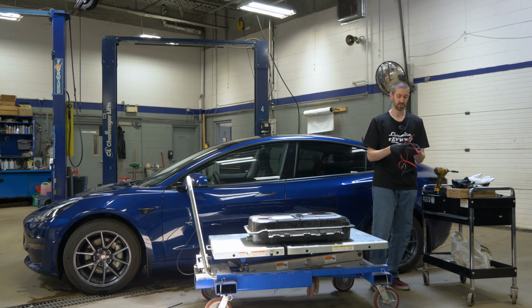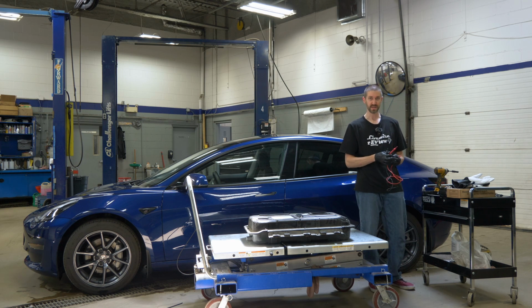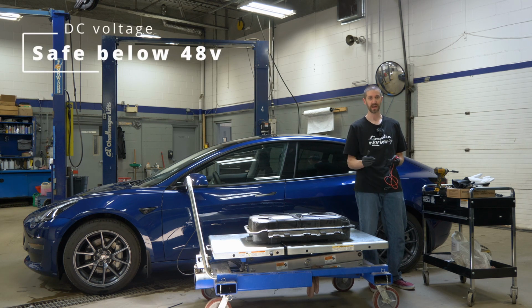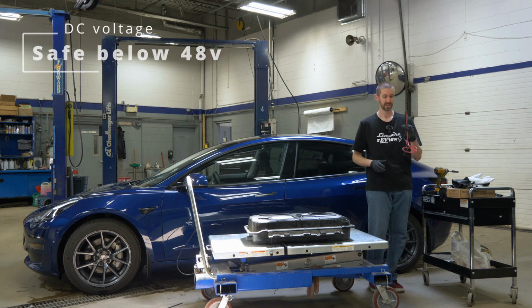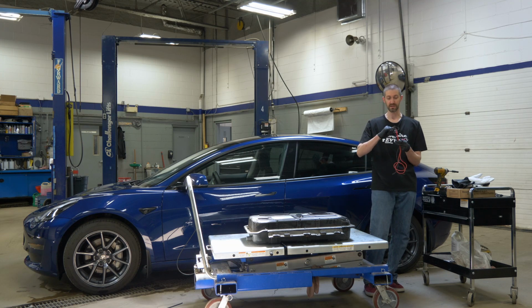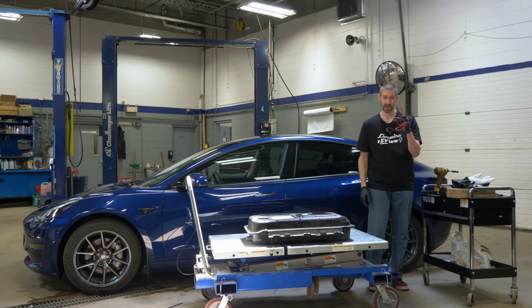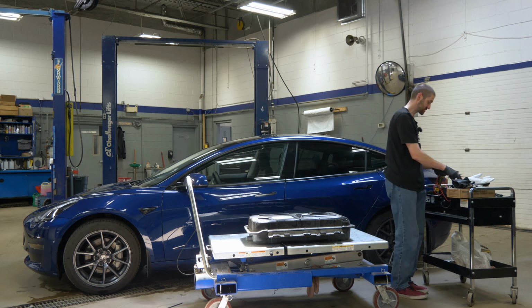Something to keep in mind when working with voltages: when it comes to DC voltage, the maximum safe DC voltage you can work with is up to 48 volts. Anything over 48 volts, you must take these precautions. Now I also have high voltage leads here. You're going to see that they have very thin tips on them. Now, the one-handed rule does make this very difficult to work with, so we're going to set this up.